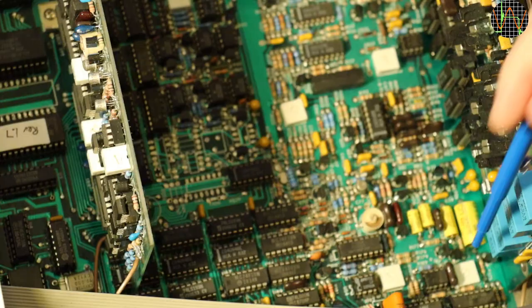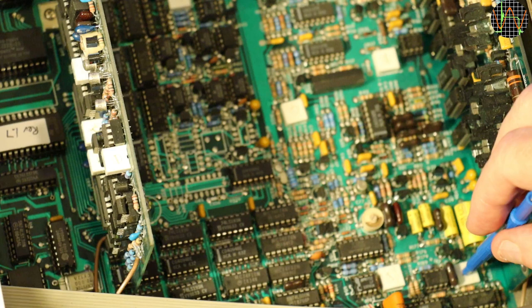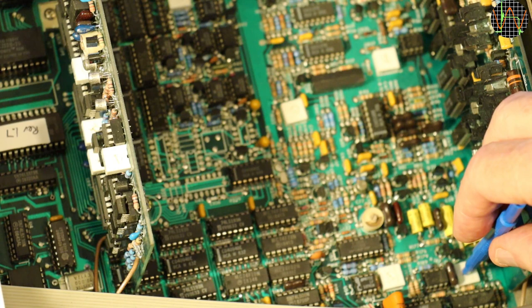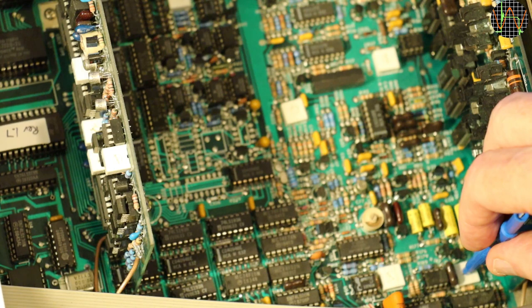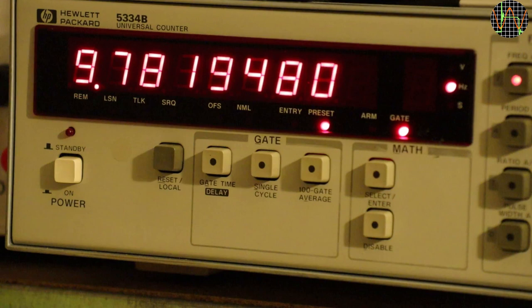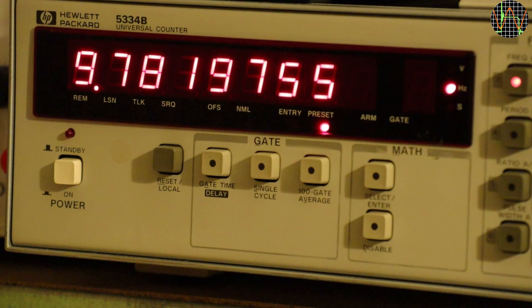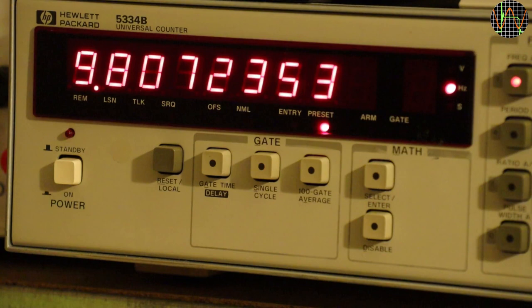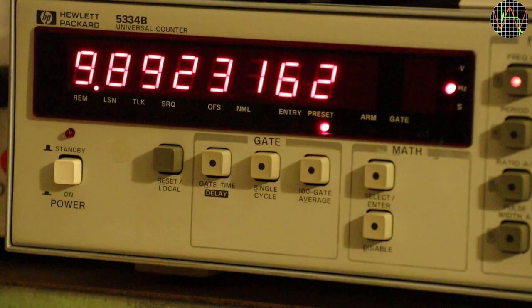Its adjustment trim pot is down in the main board and sorry I did not realize that the camera accidentally focused on the rise fall board. Anyway, there isn't much to see because the trim pot is very sensitive so the tweaks are really really tiny. The low frequency accuracy is supposed to be calibrated at 9.9Hz. It is 9.78Hz at the moment and because adjusting takes time I speed up the video a bit. In the end I decided to leave it at 9.89Hz which seems close enough for 9.9Hz.